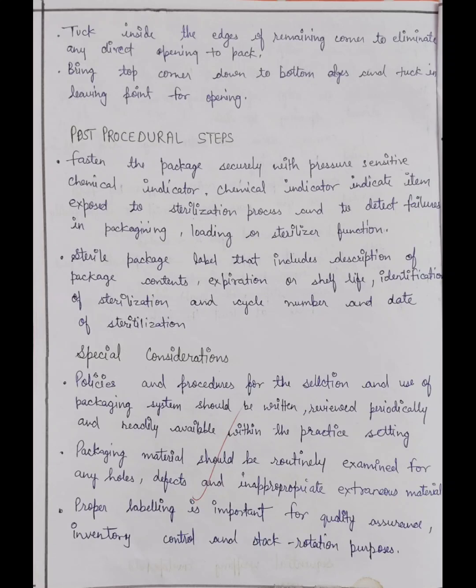Special considerations: policies and procedures for the selection and use of packaging should be written, reviewed periodically, and be readily available within the practice setting. Packaging materials should be routinely examined for any holes, defects, and inappropriate materials — check the cloth to ensure no holes, as holes cause contamination. Proper labeling is important for quality assurance, inventory control, and stock rotation. Label sets clearly so you can track which has been sent for sterilization.